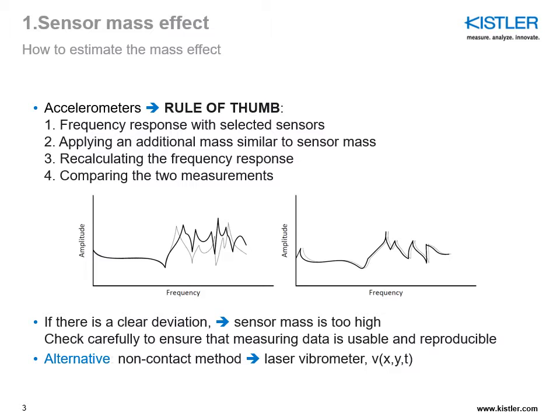Then, what you're going to do is apply an additional mass similar to the sensor mass — it could be a second sensor or a small comparable piece. Then you would re-excite your system and redo a frequency response test and compare the two measurements. If there is a clear deviation, your sensor mass is too high. Then you should check carefully to ensure that the measuring data is usable and reproducible.